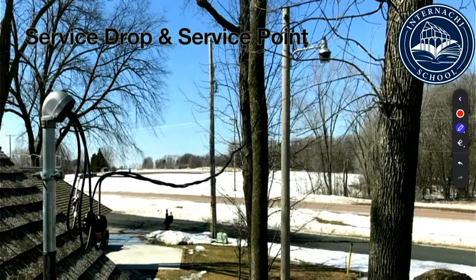Service drop, service point - again, that's where the electricity comes in. We can see our splices. Notice they put insulation on the energized conductors, but there's no covers or insulation on top of the grounded current-carrying conductor, or the neutral, or the messenger cable that comes in there. That's not a problem, that's actually normal. But the other two should be insulated.